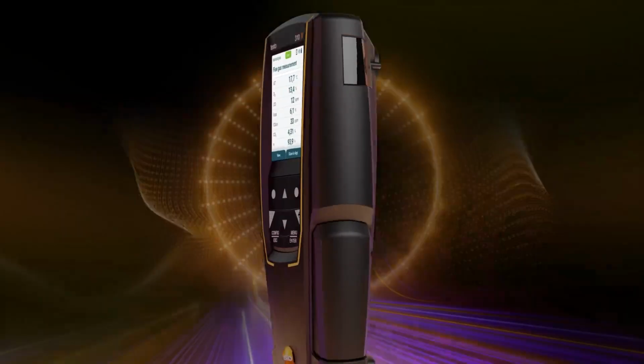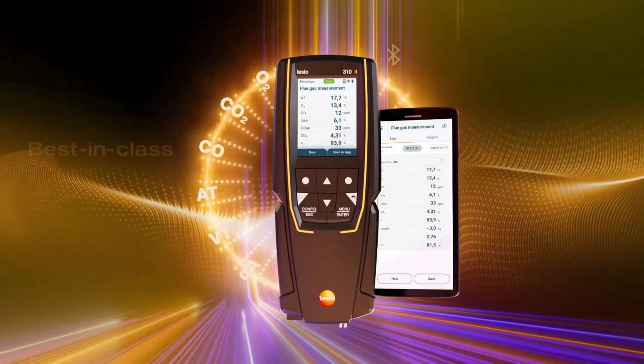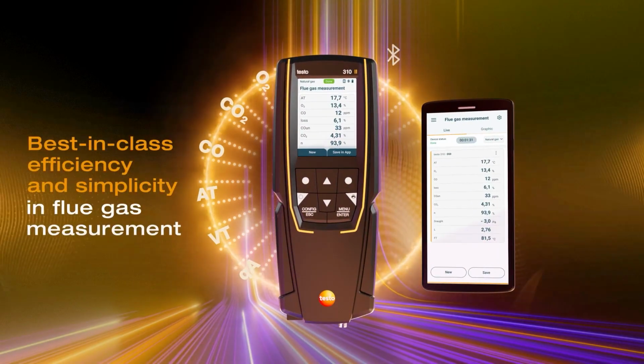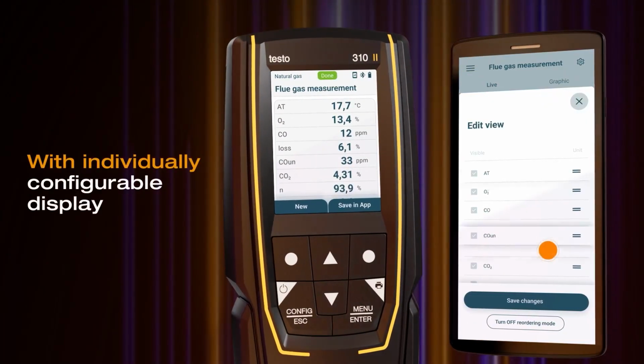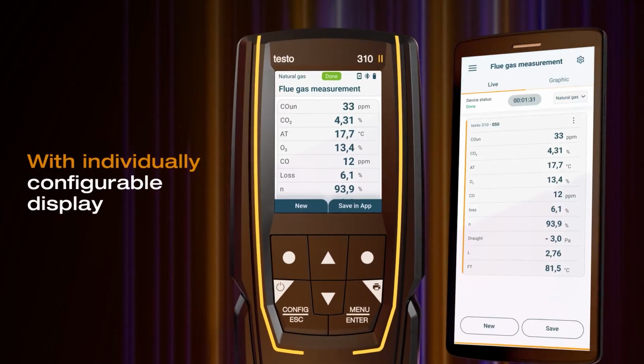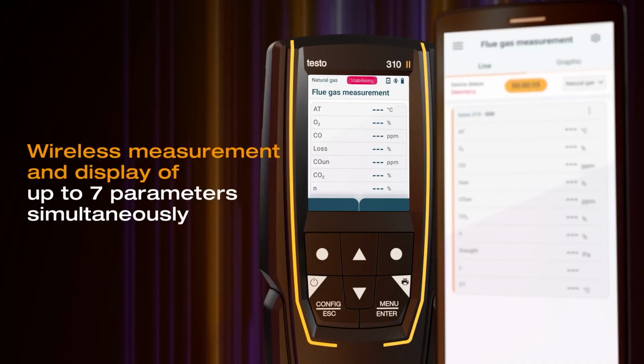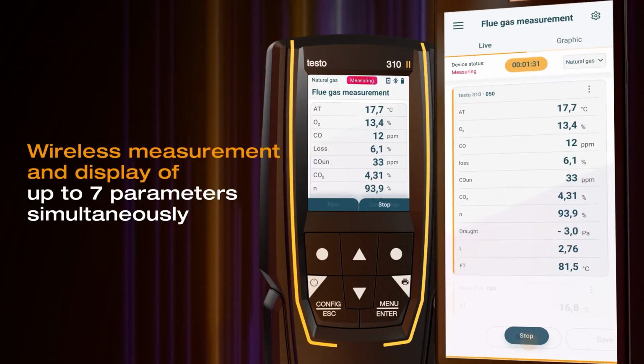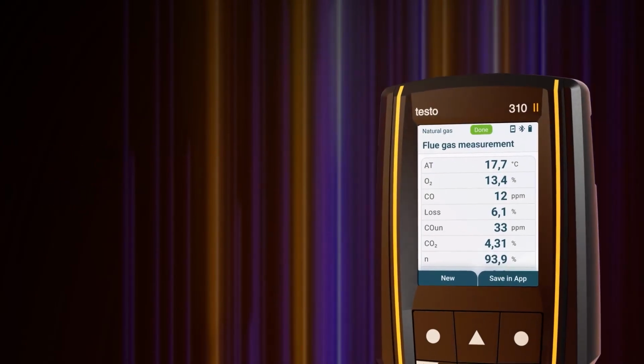The health of a system is in its combustion. The Testo 310-2 Combustion Analyzer isn't an option, it's a necessity for safety and efficiency. It precisely measures flue gas, O2, draft, and ambient CO. But the key here is the Bluetooth connectivity and Smart App.